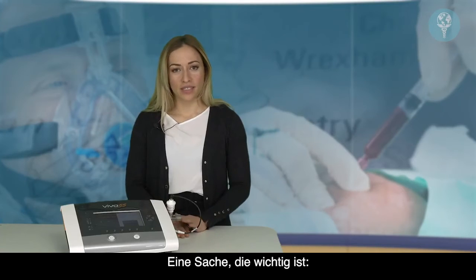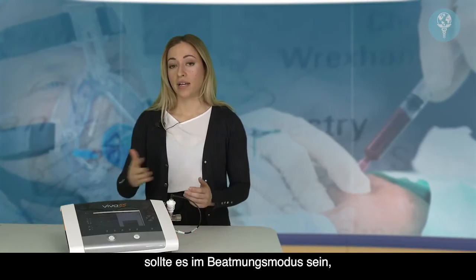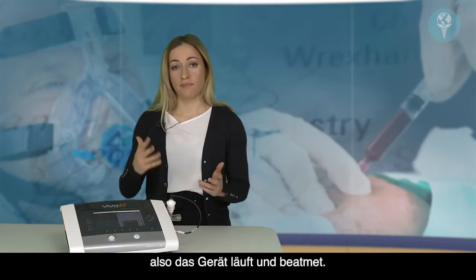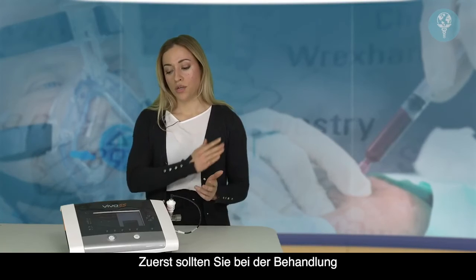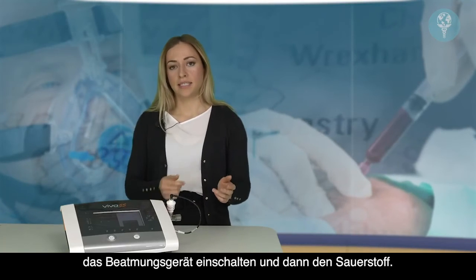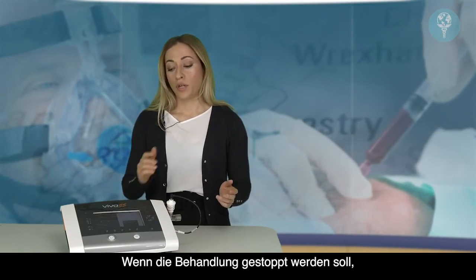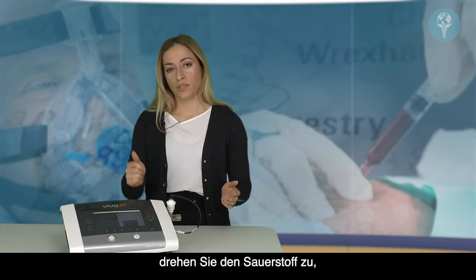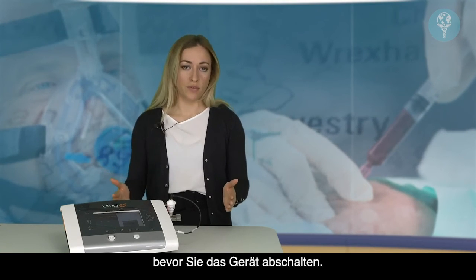One thing that's important to note when entraining oxygen through the Vivo 55 is that you should only be entraining oxygen while the device is actually running and ventilating. So make sure that you start the treatment first on the ventilator, then turn on your oxygen. When you want to stop treatment, turn off the oxygen before stopping treatment on the ventilator.